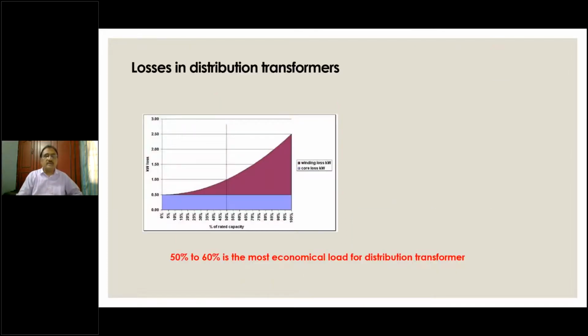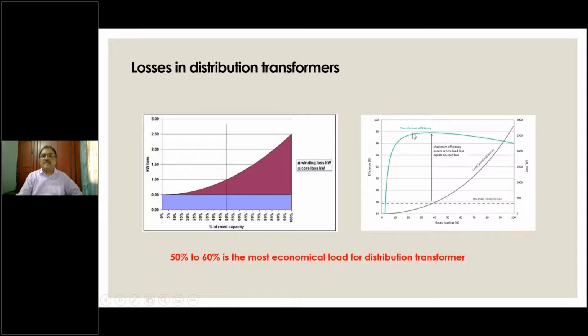Okay, now let's look at the transformer. The transformer efficiency curve will look like this. The maximum, peak efficiency will be at approximately 40% load for an oil-cooled transformer. For dry-type transformers, which the gentleman talked about this morning, the peak efficiency will be at approximately 24%, 25%, so it will be even less than that. So the best efficiency will be at approximately 40% for oil-cooled. Above that, the efficiency will keep dropping. So it is not desirable to load the transformer close to its nameplate. You should optimize. If not at 40, you should restrict it to between 50 and 60, so that after that, the effect is not felt. So this is one clue.